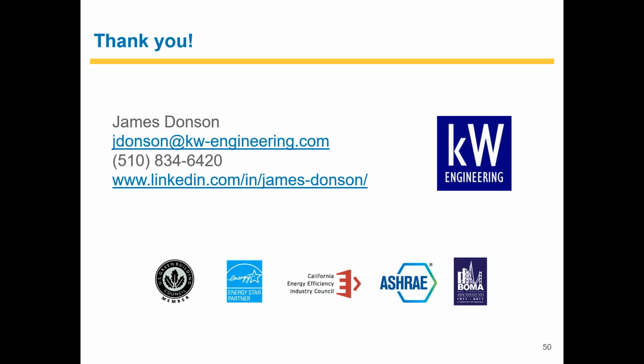In terms of figuring out what is overlit and what is underlit, my general approach is to design for IES recommended practices, and then include, maybe a week or two after the space has been retrofit and is occupied, a follow-up site visit where you're working with the tenants or the occupants to figure out what light levels are comfortable. Generally speaking, I've done some research projects where we found that people often want task tuning above and beyond what the IES calls for visual acuity. So there's some good savings to be had there. You just need the controls in order to do it.